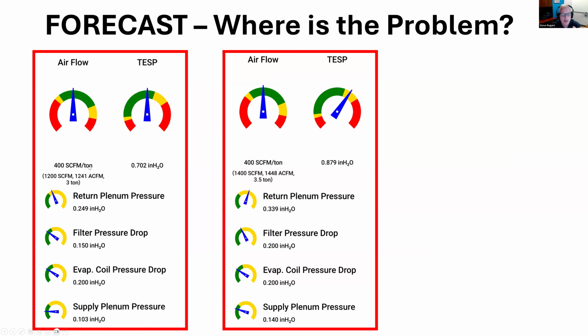So once again, I've got this broken down so I know where I should improve that system. If I really want to install the 3.5 ton system, where should I focus my efforts to improve the system? And just like before, the return is really too small. It may be that you've got the drop that's approaching the furnace. It may be that you've got not enough branches from the return, if you've got individual room returns, and the filter is also a little bit marginal at 0.2. So if I've got a bigger filter available, I might want to install that one instead.